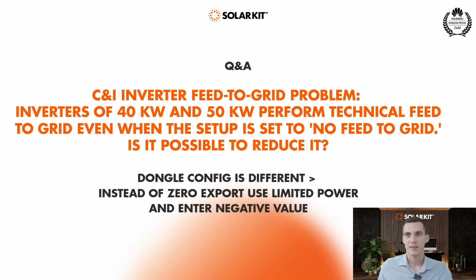And this is preset in the zero export to grid setting. I'm not sure about the value, but it's preset originally in the factory or in the R&D center. And you can use, instead of the zero export mode, a limited power mode and enter a negative value. What this would mean is that, let's say you set it to negative 100 watts, the inverter will always take the first 100 watts from the grid and then start to supply the required amount after that 100 watts.